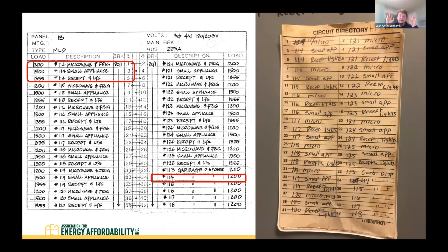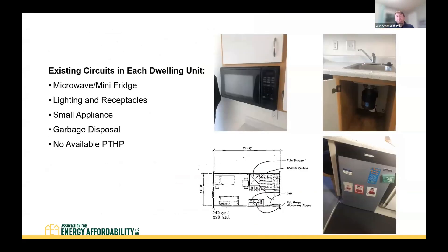Looking at the panel schedule from one of the hallway sub panels, there is no available space for additional circuits. What's highlighted in red is a single dwelling unit's circuits: a microwave and fridge circuit, a small appliance circuit, receptacles and lights, and a garbage disposal circuit. Every unit has only four circuits and no available circuit for a packaged terminal heat pump. Triggering panel upgrades would represent significant cost to the project.